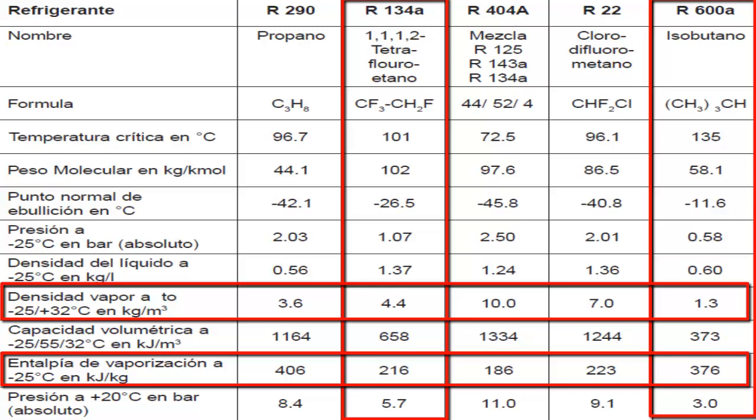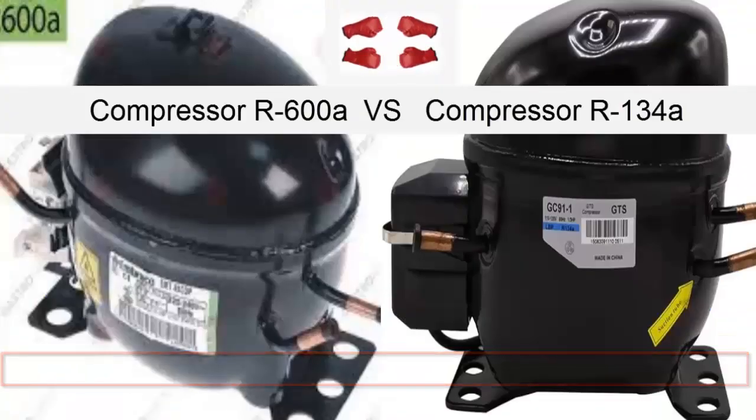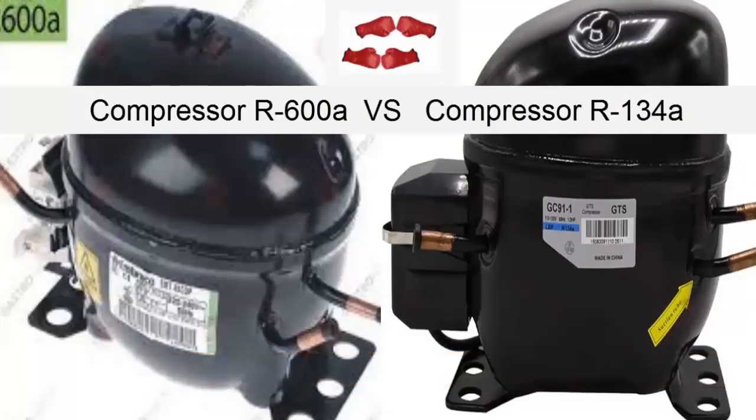A compressor using R600A handles fewer grams of gas compared to the R134A compressor, but each gram of R600A has a higher cooling capacity than a gram of R134A.